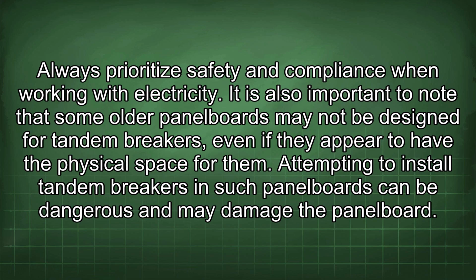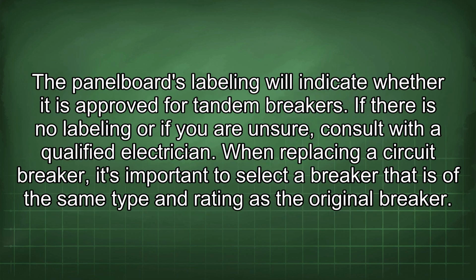It is also important to note that some older panel boards may not be designed for tandem breakers, even if they appear to have the physical space for them. Attempting to install tandem breakers in such panel boards can be dangerous and may damage the panel board. The panel board's labeling will indicate whether it is approved for tandem breakers. If there is no labeling or if you are unsure, consult with a qualified electrician.